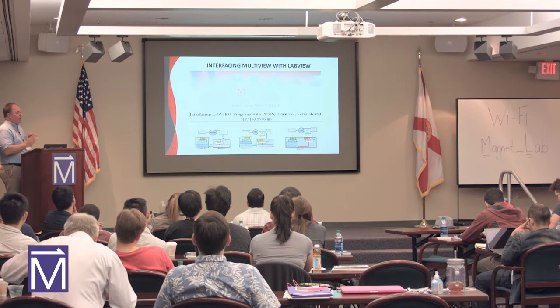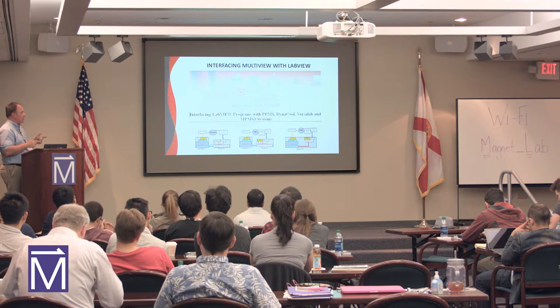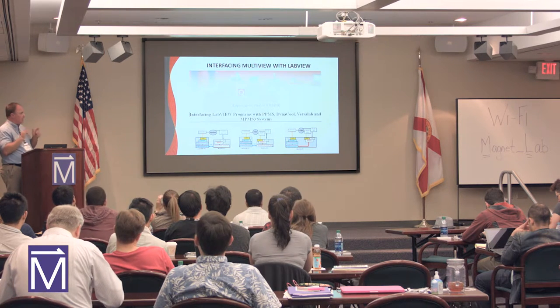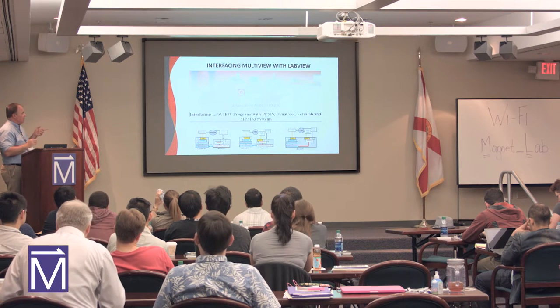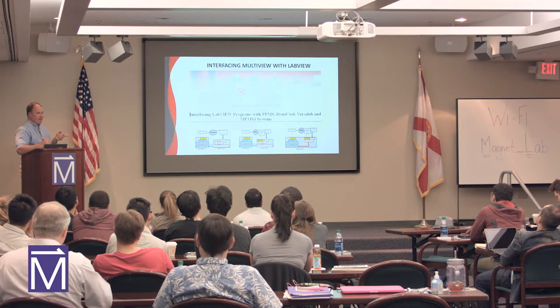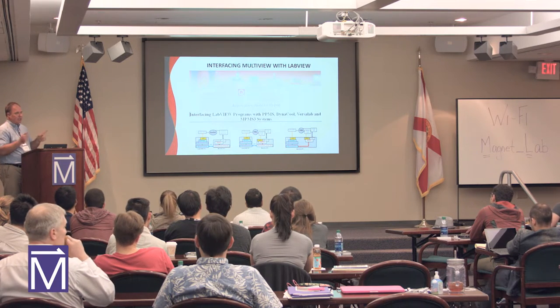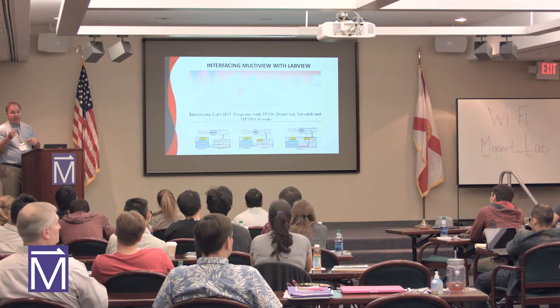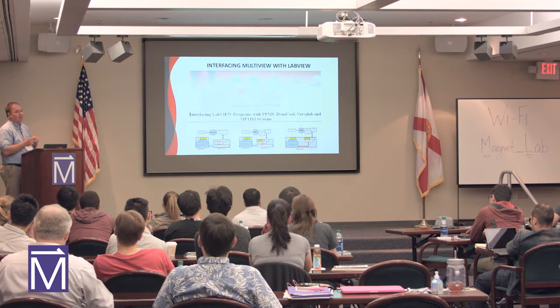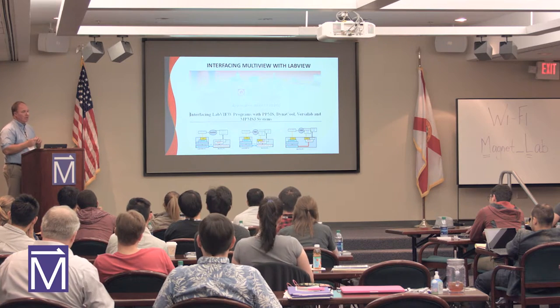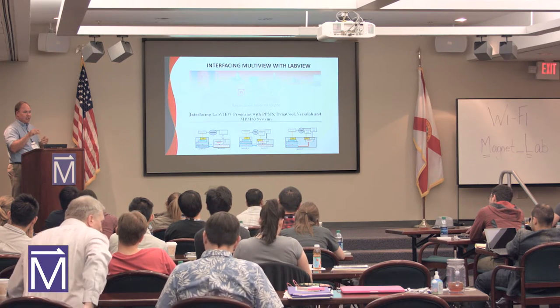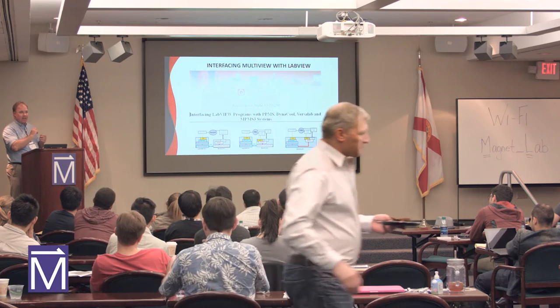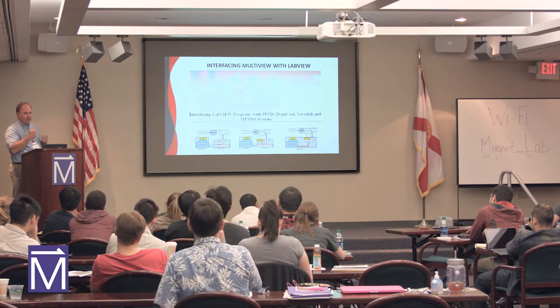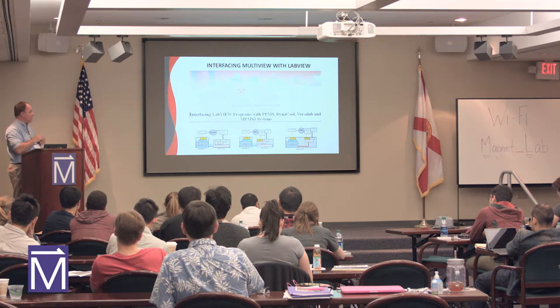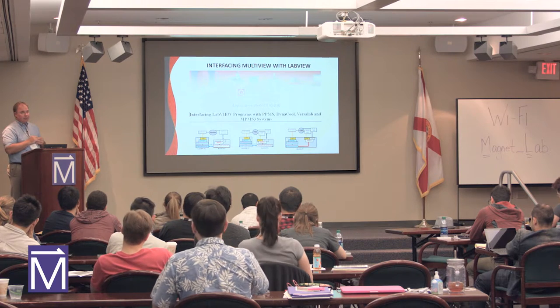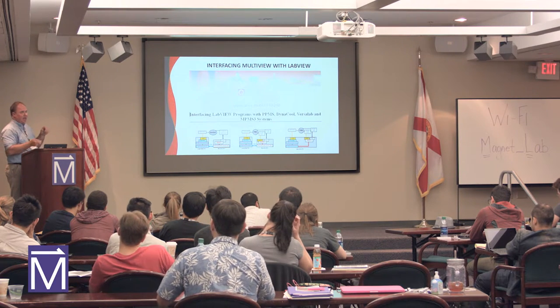There was a question asked yesterday, how do I interface my program to MultiView? So MultiView is the software platform that gives you this pile of data. We have a little DLL that you can obtain from us, and you can use that in your program to link systems together. And there was a question, do I have access to the field value in a Dynacool? And you don't have a physical connection to that value. On the old versions of the systems, you have a physical value where you can see the output of the field on the old PPMS. But on the Dynacool, it's all digital. So you can get that digital data, take it through the DLL, and then communicate.